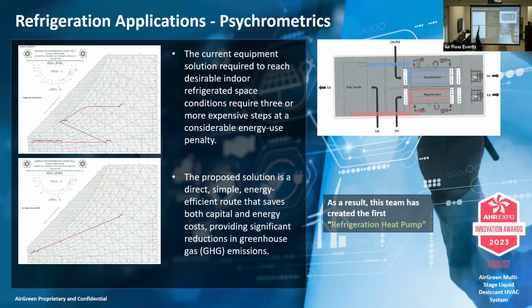One of the traditional solutions you see in the pharma world in New Jersey is that they've got 3 or 4 pieces of equipment, wheels and coils and chillers, to get all the way down into the teens. And we're able to do that once through direct. So we can go from outside air down into freezing temperatures with dew points well less than 25. And when we pushed it, we actually took our desiccant temperatures down to minus 37.